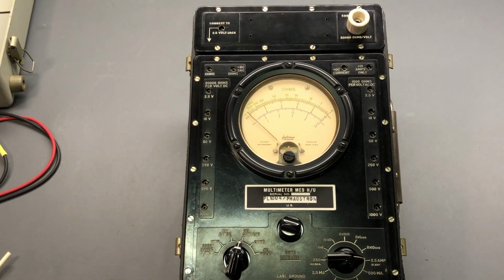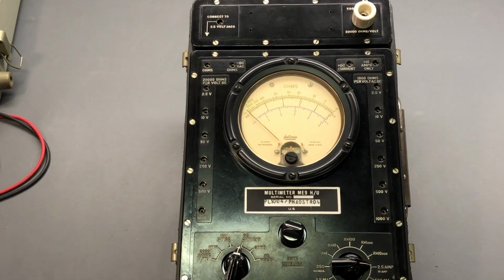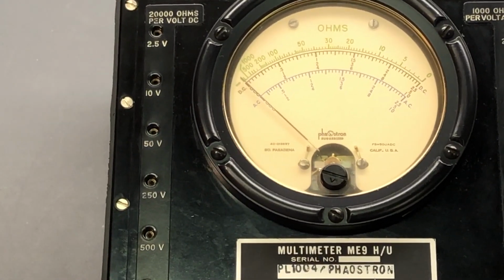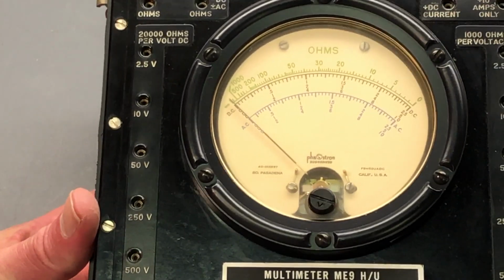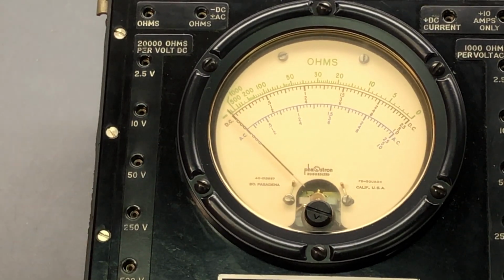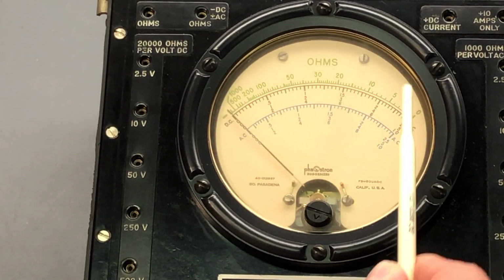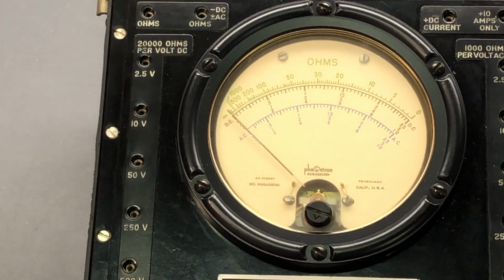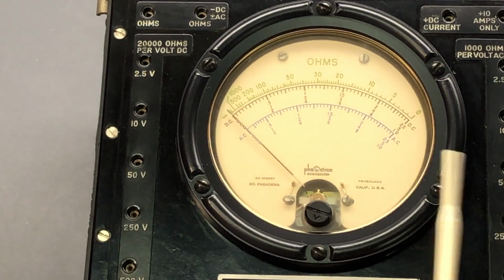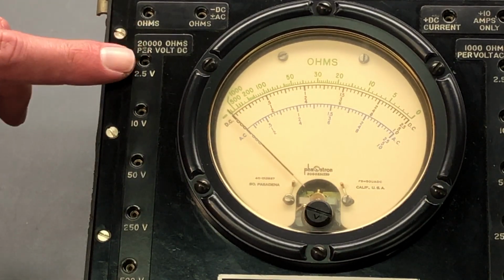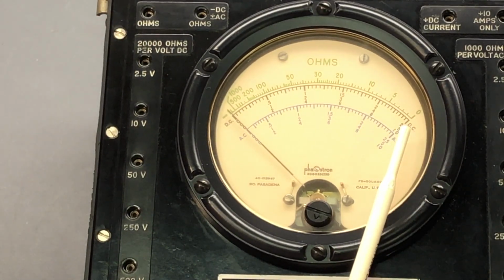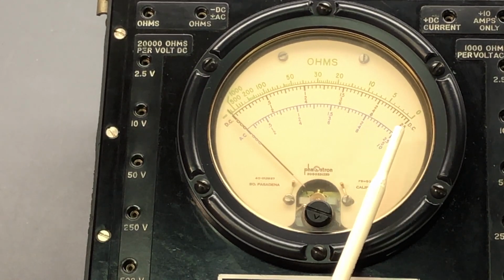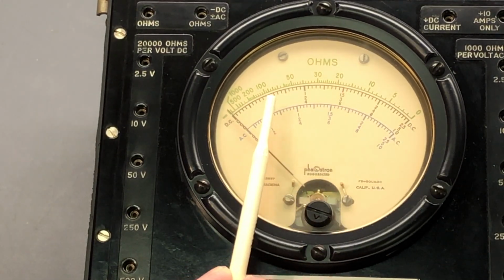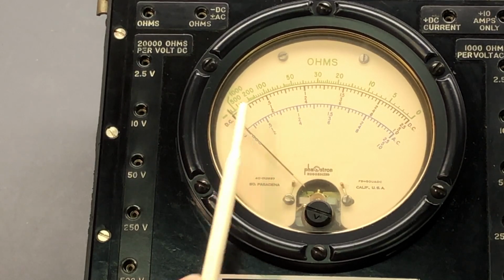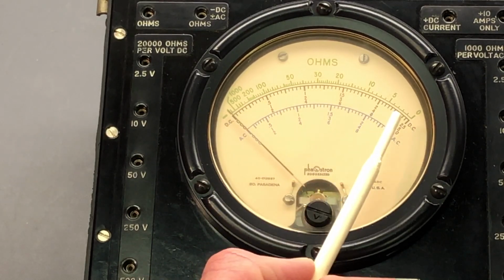I'll zoom into the meter scales and point out something here. Go down like that. That's a very nice meter, very easy to read. Colored scales. We have the blue, black, and the green colors, so very easy to read. If you are using the 5,000 volt range, even though it's on 2.5 volts over here, you're actually reading on the DC volts where it says 5, 4, 3, 2, 1, and then of course 0. Those become 1,000, 2,000, 3, 4, and 5,000.